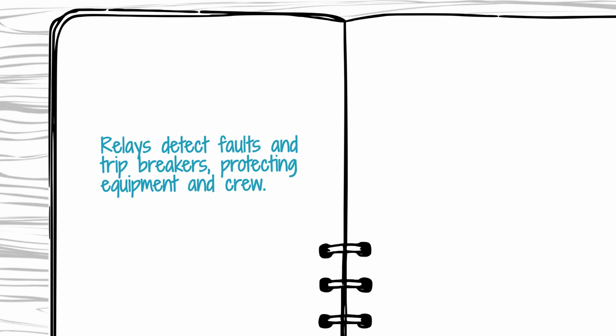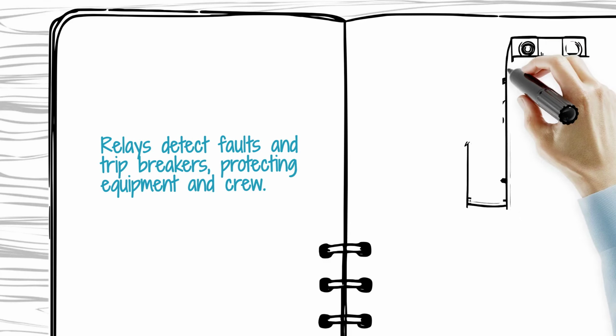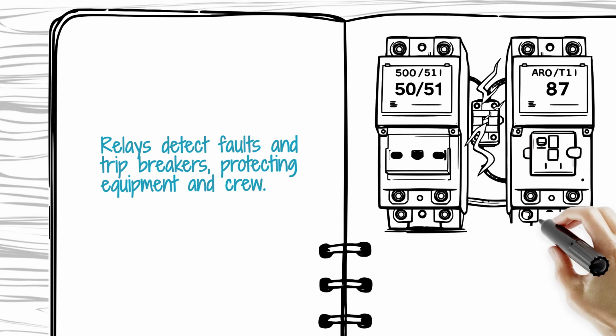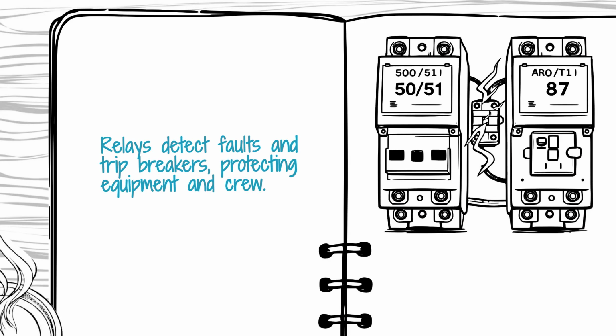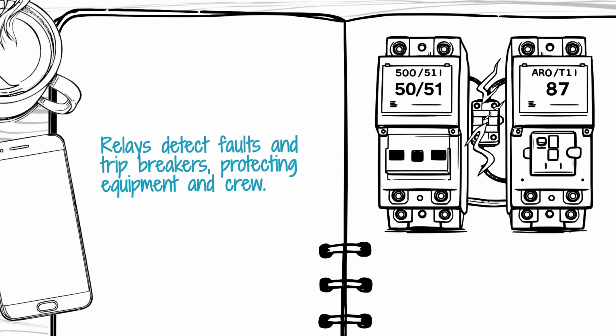Protection is provided by sophisticated protective relays, like the overcurrent 50/51 and differential 87 relays we've discussed before, which detect a fault condition and instantaneously command the circuit breaker to trip, isolating the faulty section before equipment is permanently damaged or a fire starts.